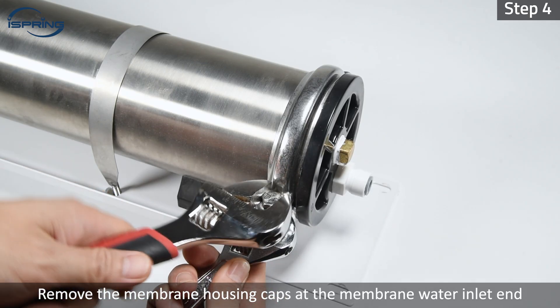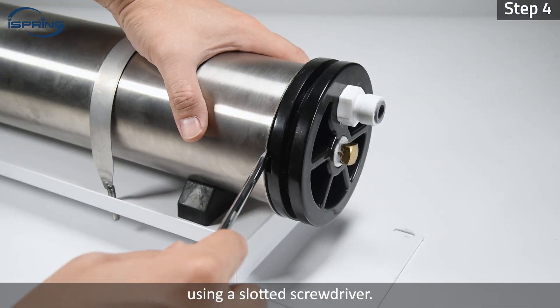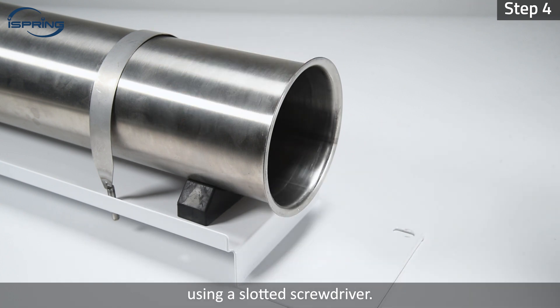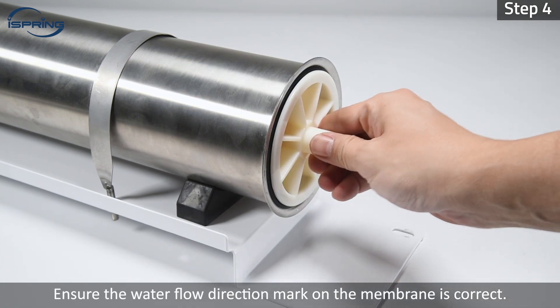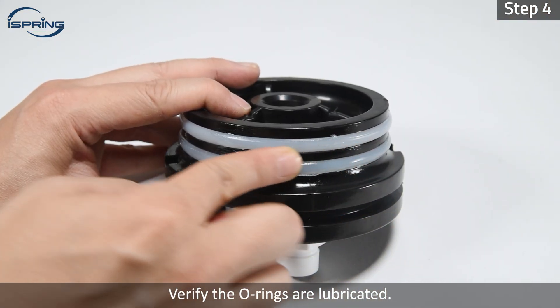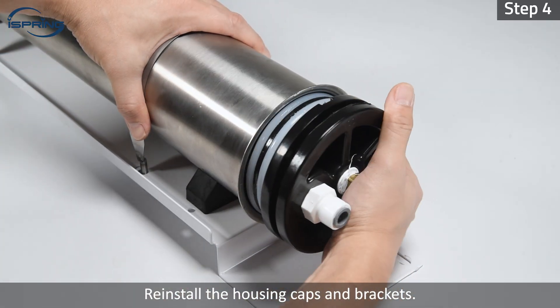Step 4: Remove the membrane housing caps at the membrane water inlet end using a slotted screwdriver. Unwrap and insert the RO membranes into the housing. Ensure the water flow direction mark on the membrane is correct. Verify the O-rings are lubricated. Reinstall the housing caps and brackets.